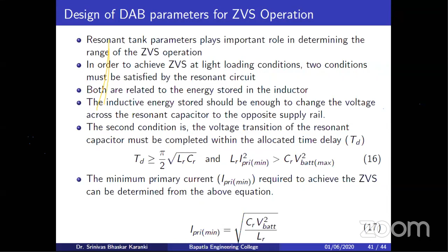For example, if I design a ZVS converter that can take a maximum load of 10 amperes, and you operate that converter in a low power range, allowing only 2 amperes to flow, then you cannot achieve zero voltage switching. This is another disadvantage: the operative range of ZVS is limited for resonant converters.